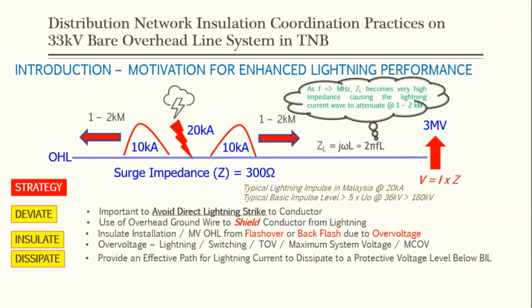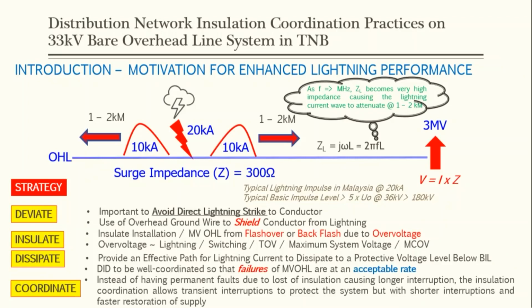Okay, and with all the deviation, insulation, and dissipation, DID, we need to coordinate, right? DID needs to be well coordinated so that failures of the medium voltage overhead lines are at an acceptable rate, as per the definition of IEEE and IEC. Instead of having permanent faults due to loss of insulation, causing longer interruption, the insulation coordination allows transient interruption to protect the system, but with shorter interruptions and faster restoration of supply. So it allows some acceptable rate of interruption, but not a permanent fault, and we have faster restoration of supply.